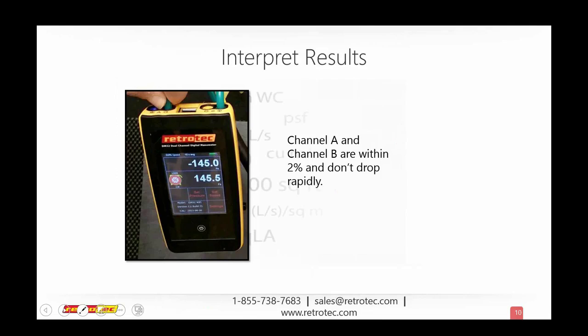Actually, you have it a bit backwards there. What we want to do is pick up separate pressures inside the building and have the same pressure on all the gauges for outside the building. So we don't want to find out how the pressures are different outside the building. We want to accumulate them all together and pull them all into one. So what I recommend you do is to run one tube through the building, tee that off as often as you need to. So you might have a tee and then a 50-foot piece on each side. If you need to get a better averaging, if your baseline is bouncing around too much, you may want to tee that off again and put another two 50-footers on the end of it. Usually the first one is enough.